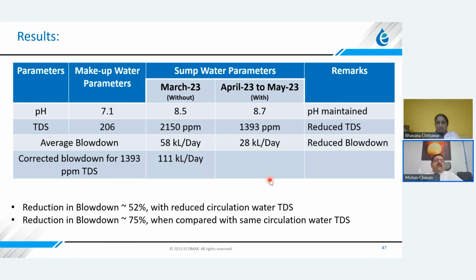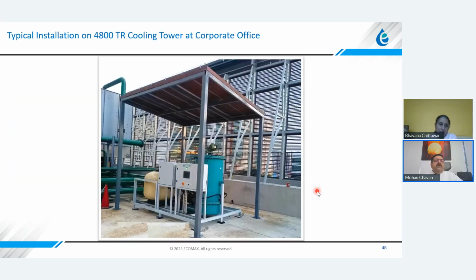So in this particular case, the requirement was to reduce the TDS from 2100 to below 1500, which is achieved by this system. And there's almost 50% reduction in the blowdown water consumption also, which was 58 meter cube per day. Now it's about 28 meter cube per day. So this technology is quite promising to reduce the water consumption substantially, mainly blowdown water consumption.